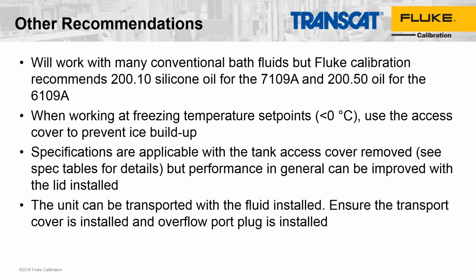And these units are designed to be transported with the fluid left inside of them. But when you do that, just make sure that the transport cover is installed. It has a nice gasket on it to seal the tank access. And there's also an overflow port plug that has to be installed. It has an O-ring in it. It seals the tank right up.